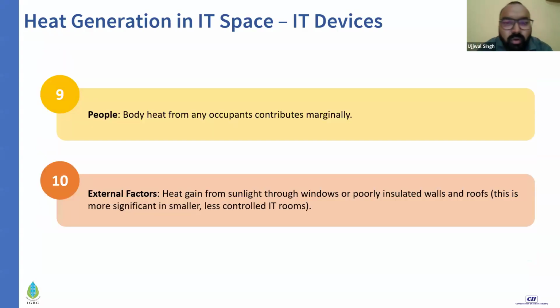People generally don't contribute a significant amount of heat to a data center, but just for our knowledge, one person is typically equivalent to between 60 to 100 watts, depending on their metabolic rate at that point in time. Since there's not much occupancy in a data center, we can eliminate it from the heat load calculation. There can also be external factors like heat gain from sunlight, windows, poorly insulated walls, etc. This is typically not common for large hyperscalers or colocation data centers, but for some small enterprise data centers, these factors still play a vital role in calculating the heat loads.